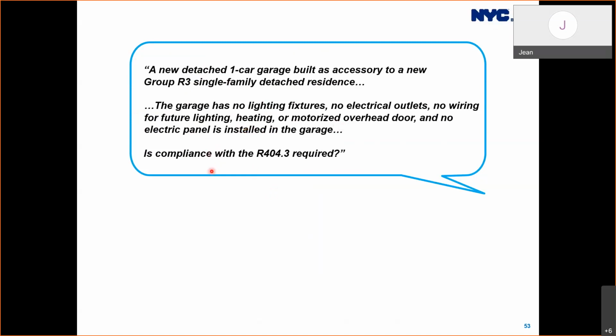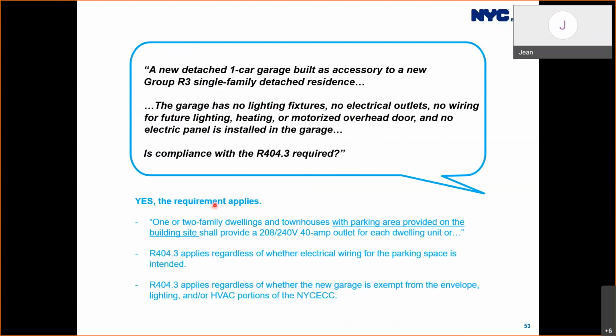So in this case, is compliance with the electric vehicle service capable requirement required? It looks like no electricity use, nor wiring for future electric power use, is intended. No lighting, no cooling. So the garage is definitely a low energy building, which will make it exempt from energy envelope requirements. So then is compliance really required? The answer is yes, the requirement applies. 1 or 2 family dwellings and townhouses with a parking area provided on the building site should provide this outlet. So this R404.3 applies regardless of whether electrical wiring for the parking space is intended.